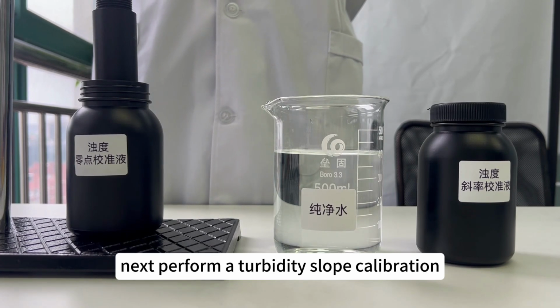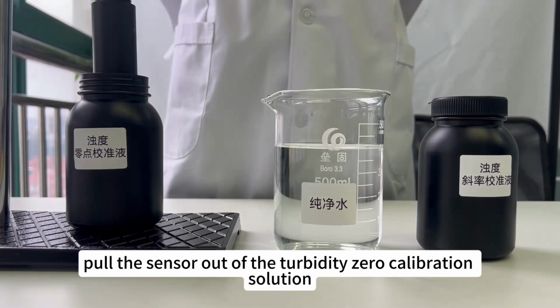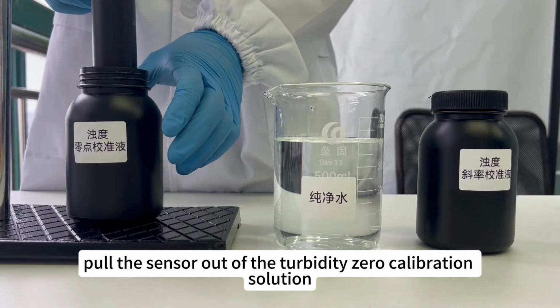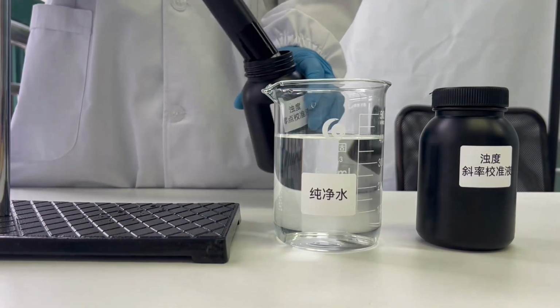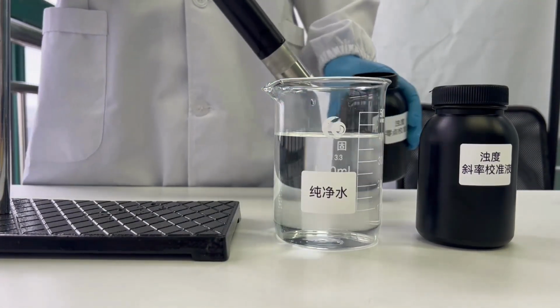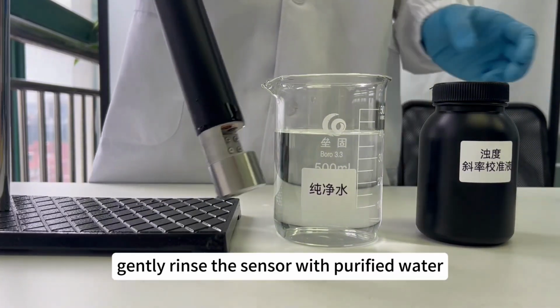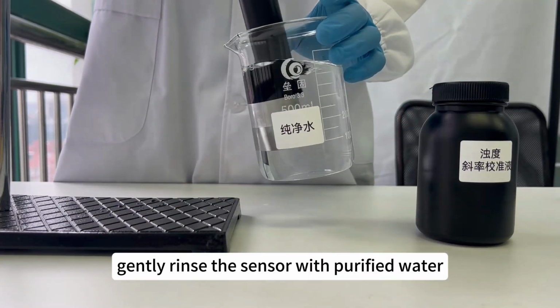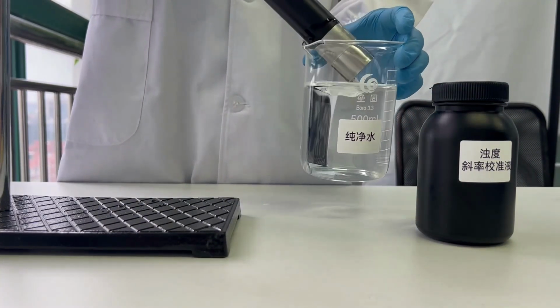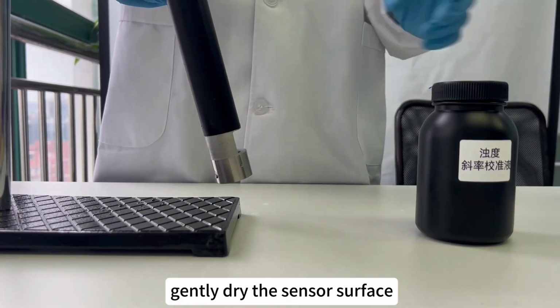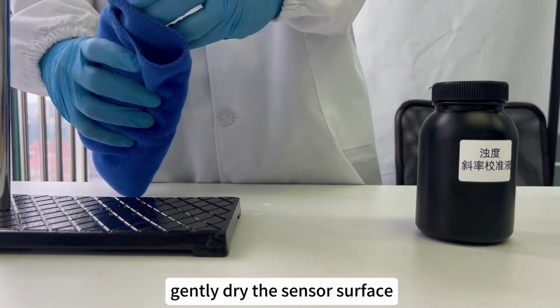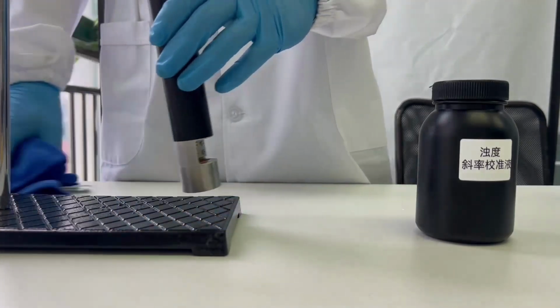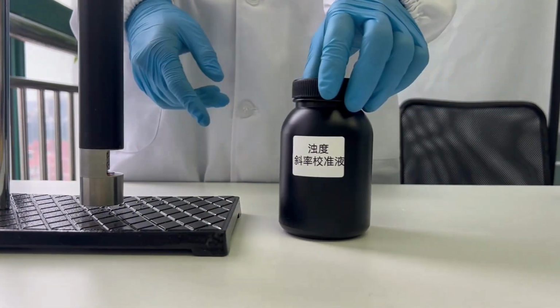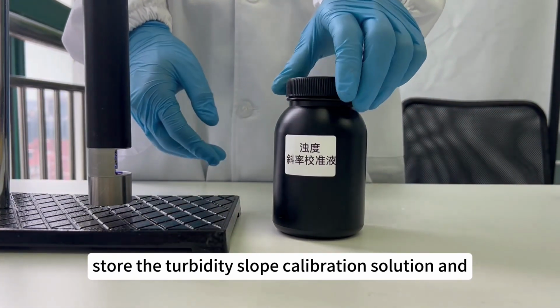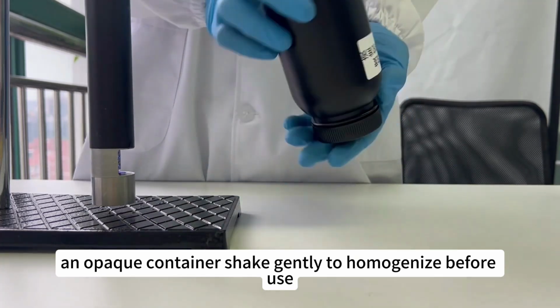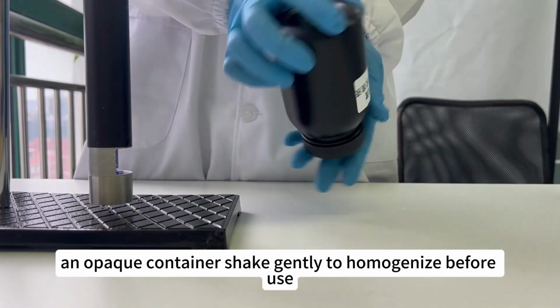Next, perform a turbidity slope calibration. Pull the sensor out of the turbidity zero calibration solution. Gently rinse the sensor with purified water. Gently dry the sensor surface. Store the turbidity slope calibration solution in an opaque container. Shake gently to homogenize before use.